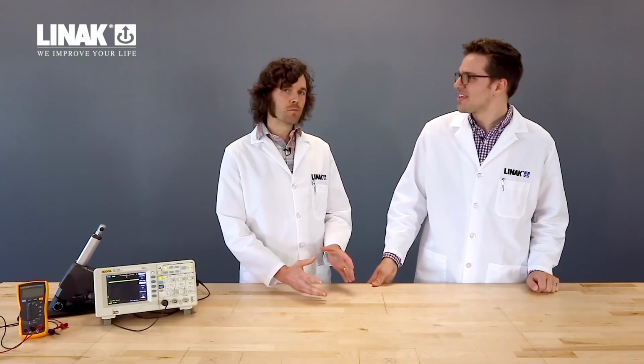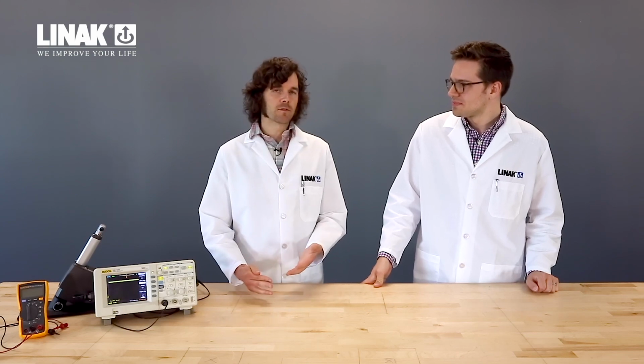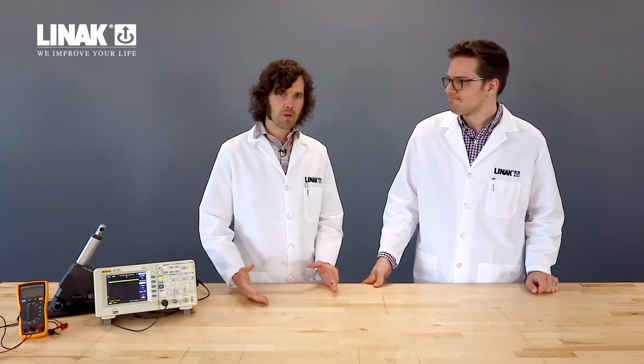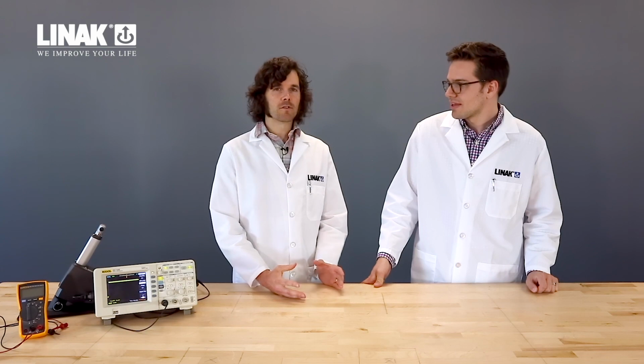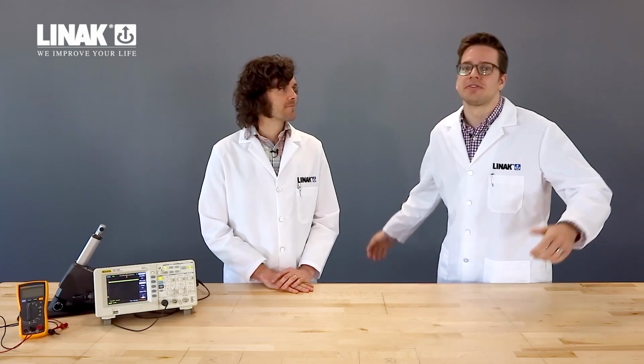That's right. We have absolute positioning, which would be positions stored in mechanical means, so that if the actuator were to be powered down, it moves, and then power up again, it's still going to be accurate. And then there's relative positioning, which is more like a count-based type. That's right. It's a lot like if you're to climb a ladder and determine your position on that ladder by just the number of rungs you've grabbed rather than, say, looking down.